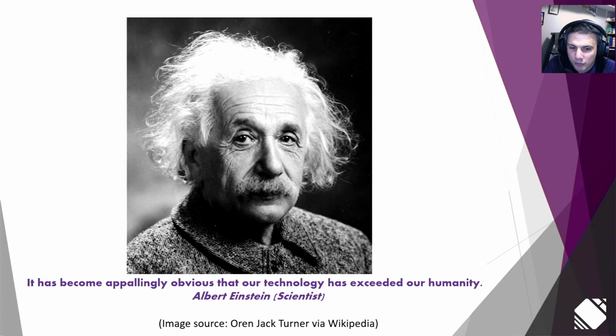Say, okay, all these things are still cool, but if a contractor enters this area, are they safe? If they're not safe, is there a way I can change the design so that they are intrinsically safe? If they're walking in a switch yard for 230,000 volts, they shouldn't have to worry that the substation is going to arc to them, through their body, into the earth, killing them. They should be aware that there's a zone of protection, that the cable is high enough in the air that they're not going to have to worry about getting arced.